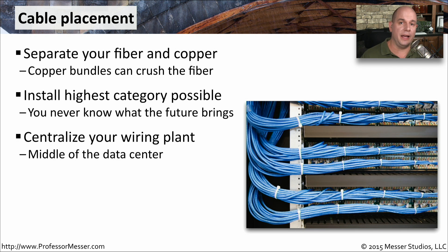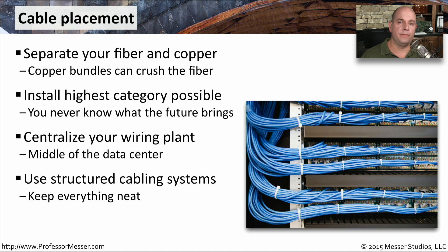You should also think about centralizing your wiring plant. On each floor, the wiring closet should be in the center of the floor, and in your data center you want to have everything come back to a central point. These cables and fibers are the foundation of your network — if they are not installed properly, nothing is going to work properly. So you want to be sure to use a structured cabling system and keep everything as neat as possible. If you're having a problem on your network, you want to be sure that problem is never happening because of your physical infrastructure.